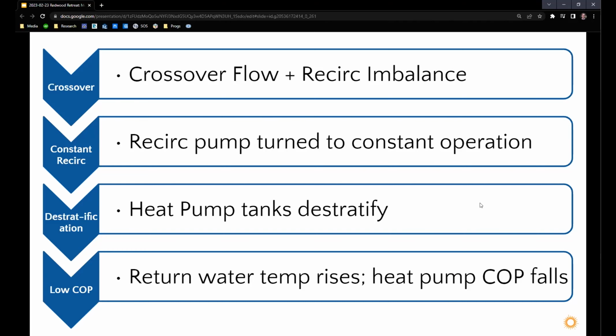So what maintenance managers do, they know how to resolve this. You can just crank the recirc pump higher, you install a bigger recirc pump, or you crank up the temperature of the boiler, and then you symptomatically address the crossover flow by whisking it away with a recirculation pump. That doesn't work super well with heat pumps. And in the most extreme examples, crossover flow can become a very significant proportion. I did a study for NYSERDA on solar thermal systems where we proved that at one building in the Bronx, over 80% of all incoming cold water to that particular building was coming in through crossover.